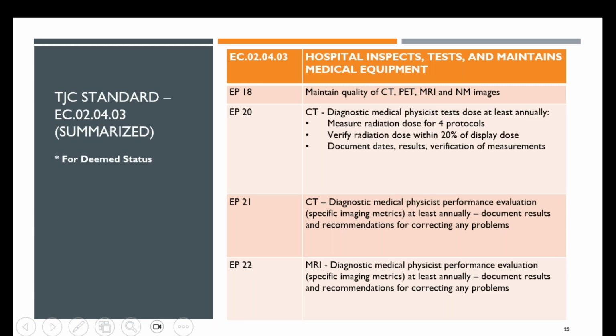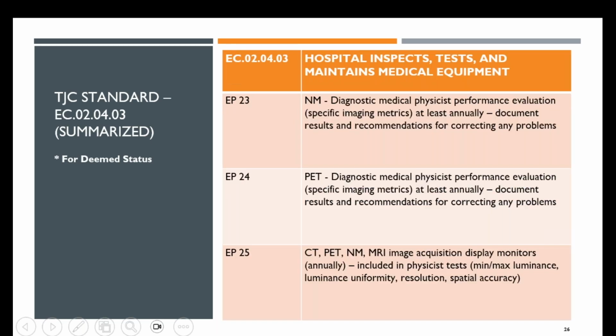So a diagnostic medical physicist must test the radiation dose produced by the CT at least annually. And there are specifics in the standard on how that test should be conducted. Also, a diagnostic medical physicist must conduct a performance evaluation at least annually, following specified metrics, and document the results and recommendations for correcting any problems. This needs to be done for CT and MR, which are specific to this slide, but it also needs to be done for nuke med and PET as well. Each lists different specifics for the evaluation though, so please refer back to the full standards for each modality. And additionally, for CT, PET, nuke med, and MR, the annual performance evaluation conducted by the medical physicist must also include testing of the image acquisition display monitors for the parameters that are listed.